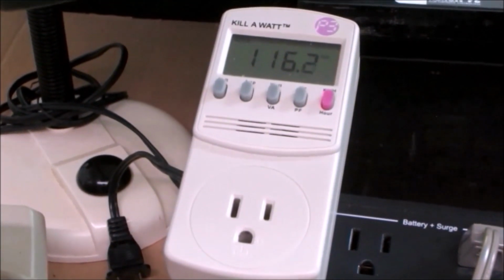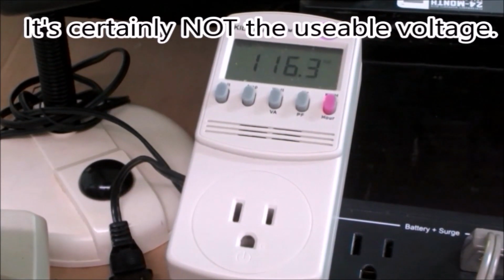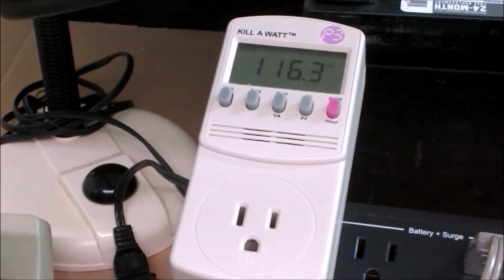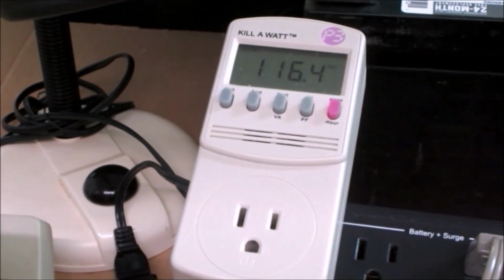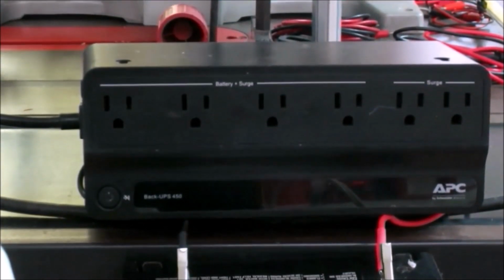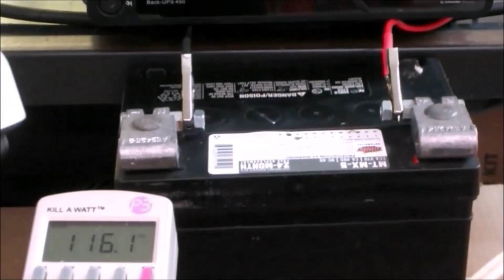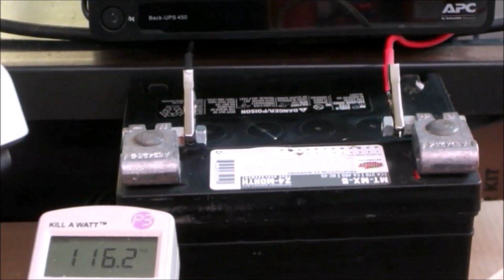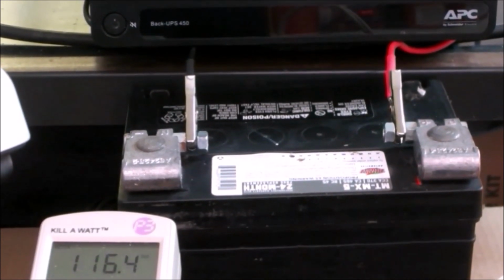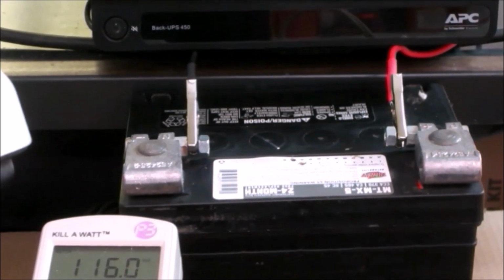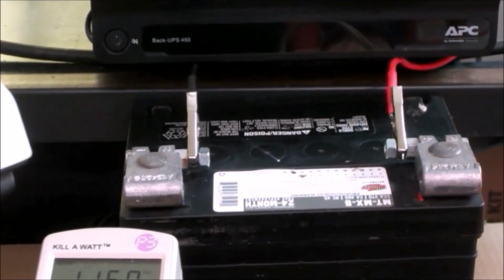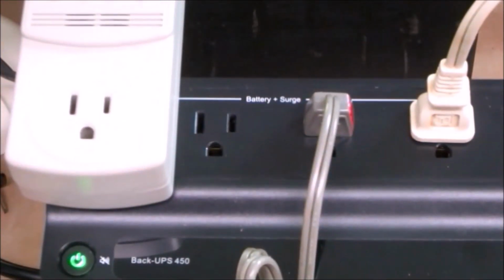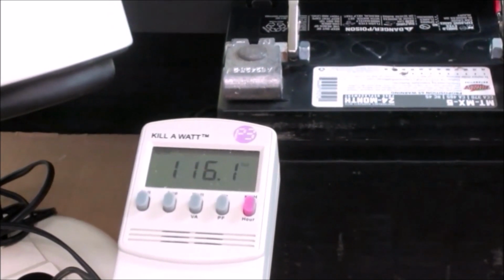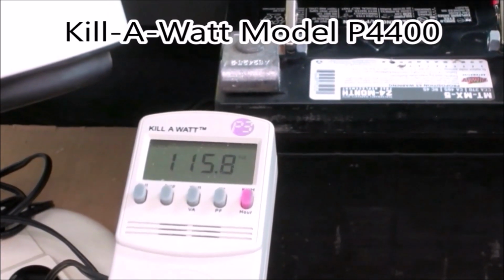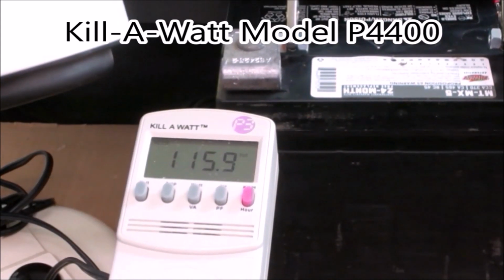That can't be RMS voltage. Now, a lot of you are going to say, well, your internal battery is weak, and that's why you're experiencing this. But that's not the case. I have a second unit here, and I've modified that unit to work on an external battery, so that we could monitor the voltage of that external battery. If we were running on that unit right now, you'd see that external battery is up around 13 volts. And so is this internal one. It's a perfectly good battery inside this unit. We've experienced a brownout, but the Kill-A-Watt, which is supposed to be true RMS, is not showing it.